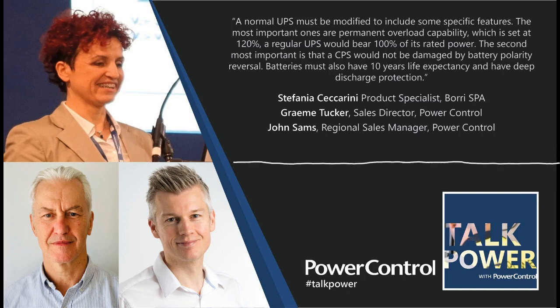This time we're talking about how UPS systems can be modified to comply with Central Power Supply System standards, BS EN50171. This standard specifies the general requirements for CPSS for an independent energy supply to essential life safety equipment. With me to discuss this topic is Stefania Ceccarini, Product Specialist at Borri SPA, Graeme Tucker, Sales Director at Power Control, and John Sams, Regional Sales Manager at Power Control. Graeme, can you start us off with an overview of the standard?